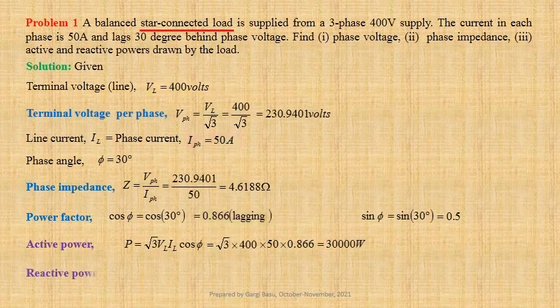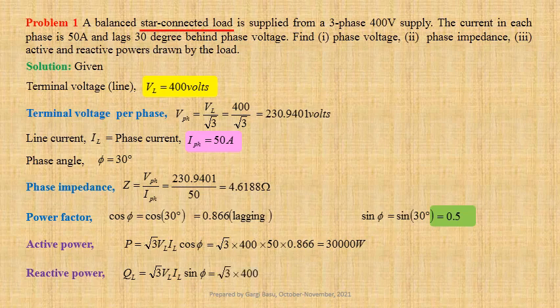Reactive power QL equals root three times VL into IL sin phi. Using values we get root three into 400 into 50 into 0.5, that gives us 17,320.51 volt ampere reactive.